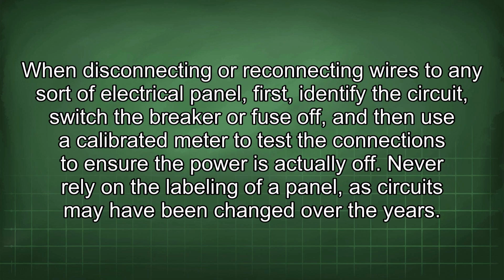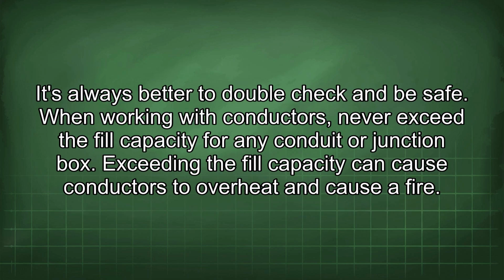When disconnecting or reconnecting wires to any sort of electrical panel, first identify the circuit, switch the breaker or fuse off, and then use a calibrated meter to test the connections to ensure the power is actually off. Never rely on the labeling of a panel, as circuits may have been changed over the years. It's always better to double check and be safe.